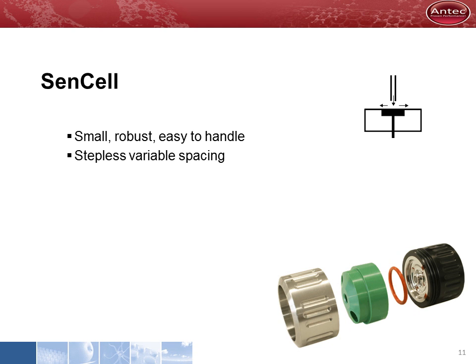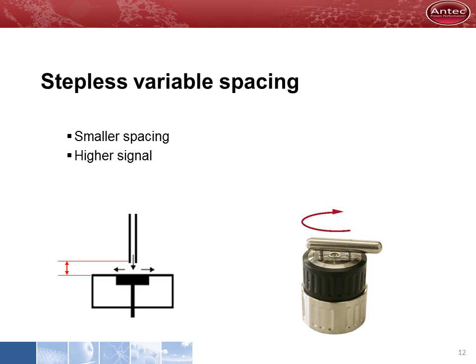The SenCell is a wall jet cell designed for the highest sensitivity. The cell is small, robust and easy to handle. Instead of a polymer spacer, it has stepless variable spacing. In a turn of the hand, the spacing can be set from wide to almost zero micrometers. This allows for tuning of a method for best possible detection performance.